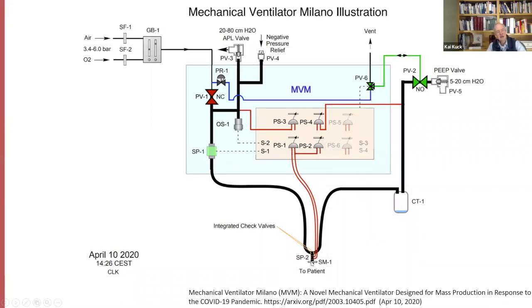You can also see here, right at the Y piece on the clean side of that antimicrobial filter, there's a flow sensor, a differential pressure flow sensor. You can measure differential pressure from that flow, and then they ran a line so you also know the absolute pressure in the airway right at that point. And then there's a second one here. I don't know why, maybe because it's more accurate as far as PEEP goes. They also have supply pressure sensors to make sure you have supplies. And up here on the right side, we have an oxygen sensor, so that if you dialed in a certain oxygen concentration, you can confirm that it's correct.